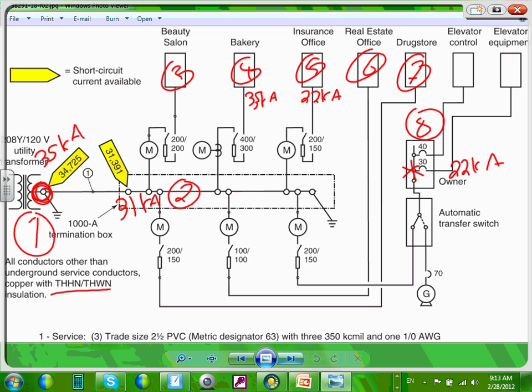We only care about panels. Loads downstream, not a big deal. Only panels and distribution systems. I can do the calculation and find the short circuit right at this elevator equipment, the elevator control panel, if I need to. Most of the time we stop at the panels, guys. Usually 100 amp panels or higher, that's what we do the calculation on.